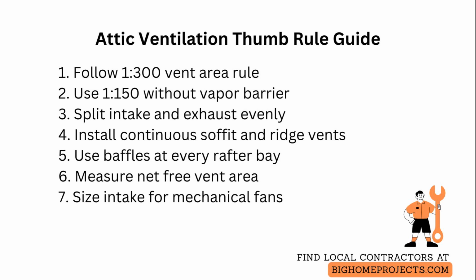Measure net-free vent area using manufacturer data, not just raw opening area, because screens and louvers reduce free area significantly, and you must account for that when calculating total openings. When using mechanical exhaust fans, size intake accordingly so negative pressure does not draw conditioned air from the living space through leaks, and so makeup air is routed through the designed soffit intake.